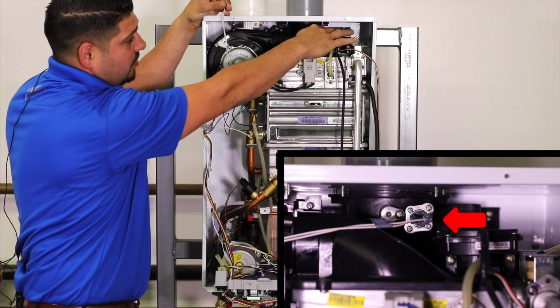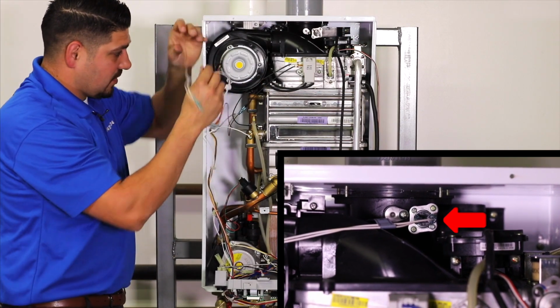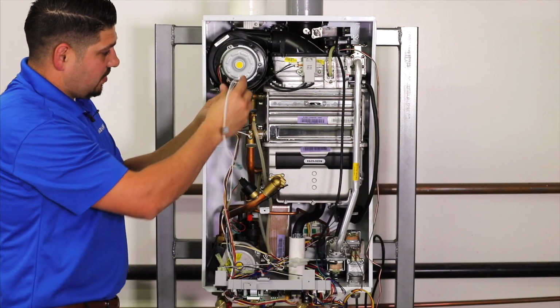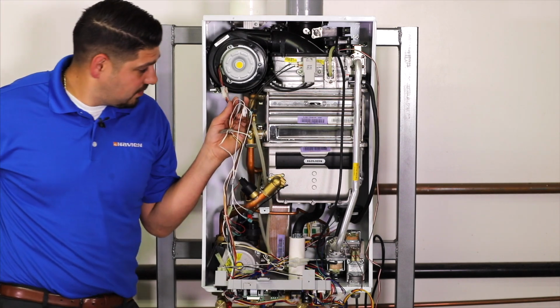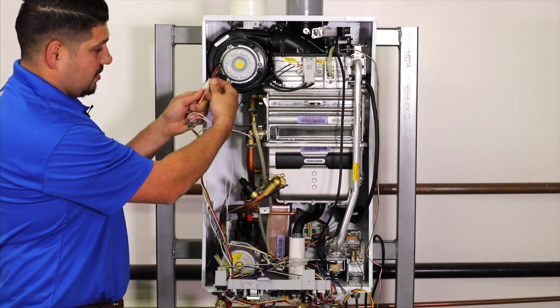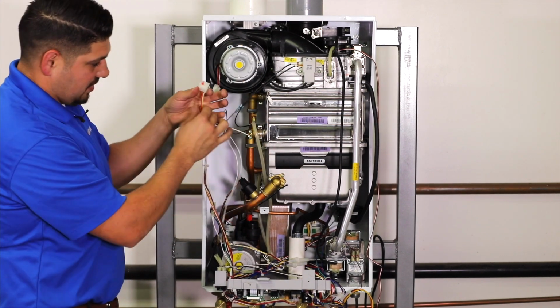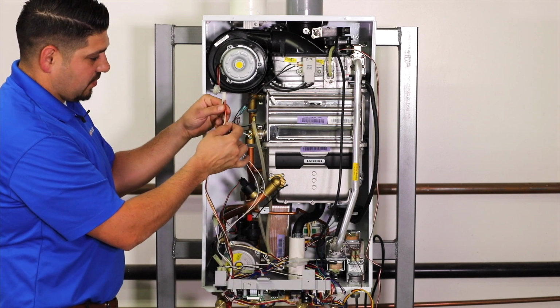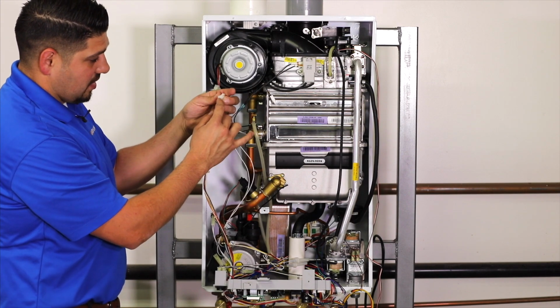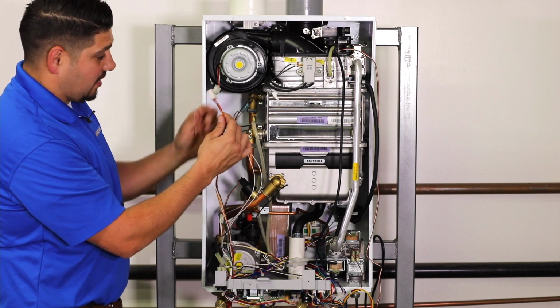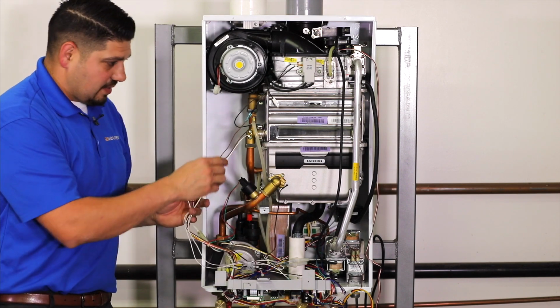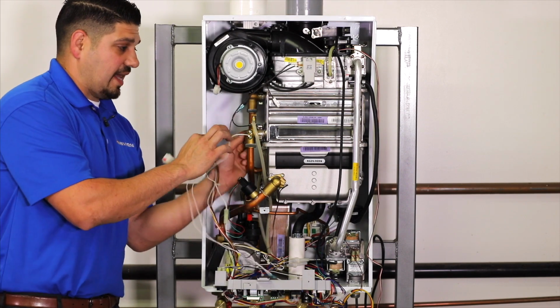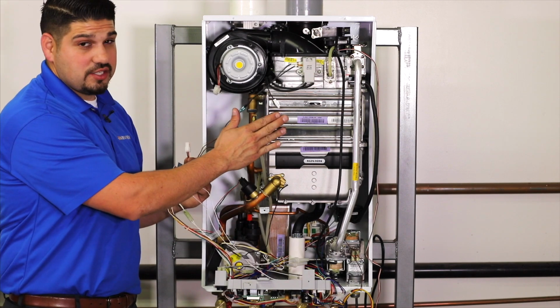These 2 white wires went to a high limit on your exhaust. I'm going to keep going down a little bit. We're going to disconnect this Molex connector to your fan. It's a pretty big plug. It's everything from a red, orange, black, white, and yellow wire. Then you have a high limit located on the side of your heat exchanger.